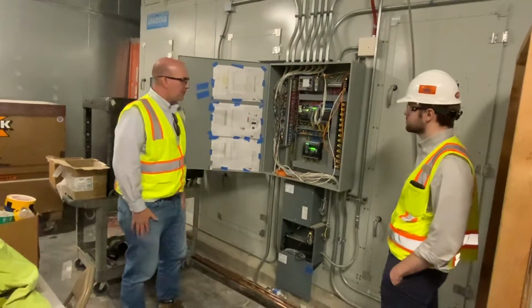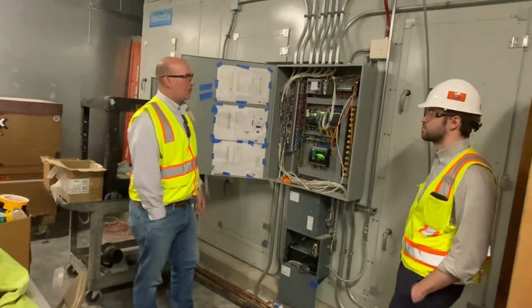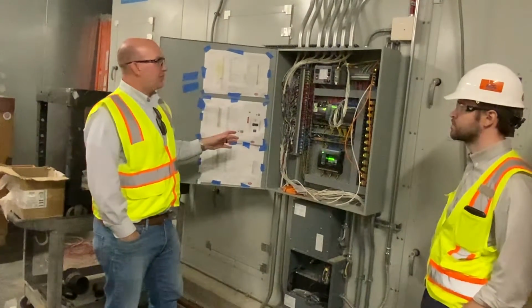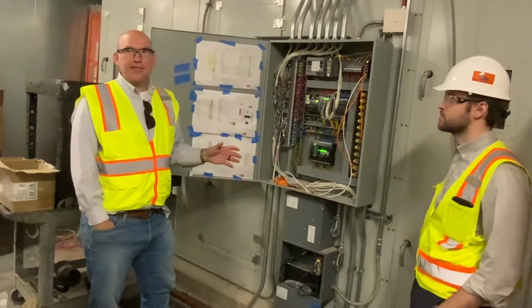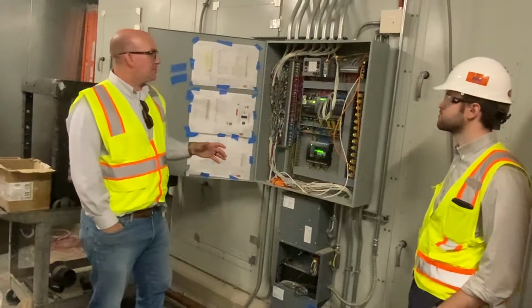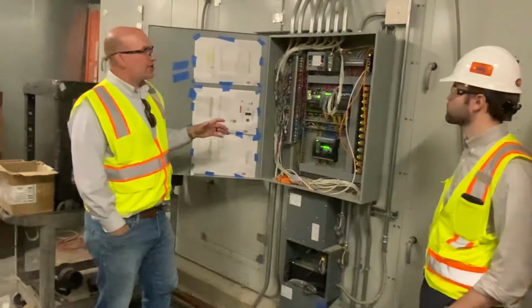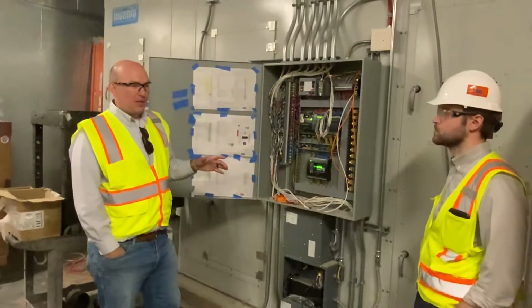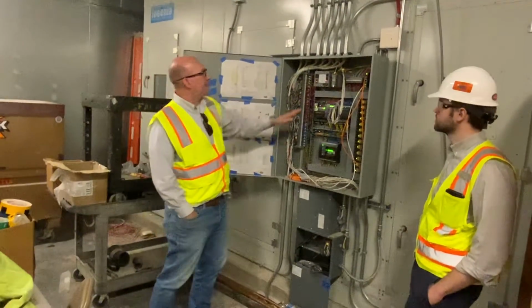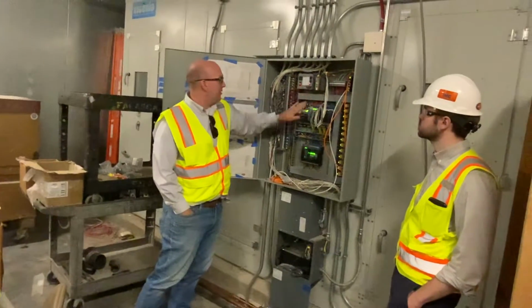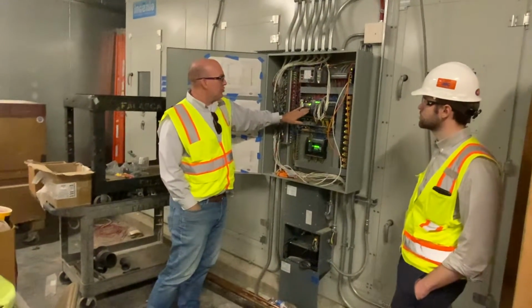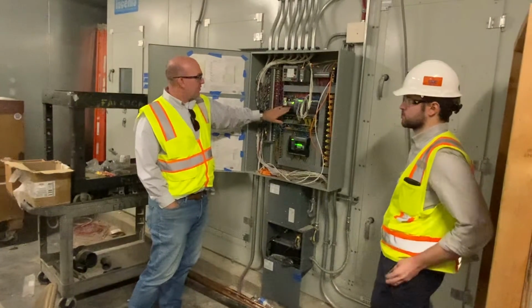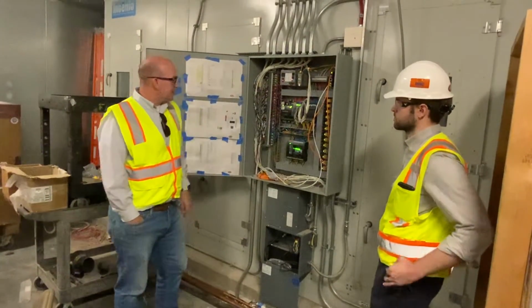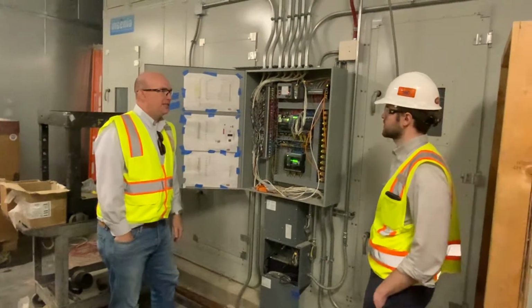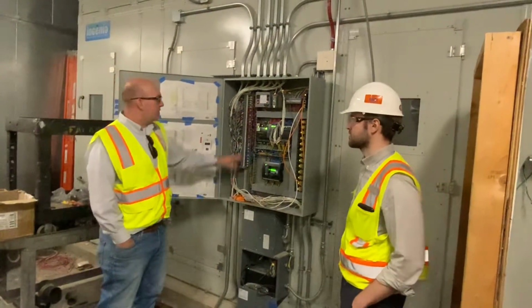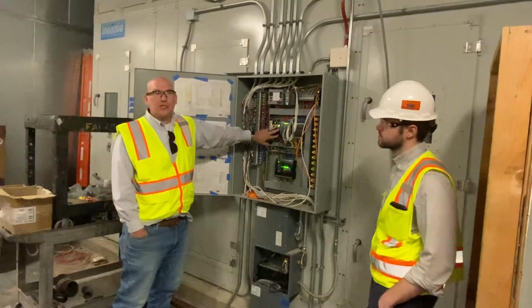Now, if you're familiar with the older installations of Automated Logic, most contractors are using regular AC transformers to power the controllers. There's a significant savings of size, not so much cost. It's a little more expensive to use DC power supplies, which is what we have here. The real savings comes in the draw from the controller. For this controller and expander, you would need, is it a full 100 VA or is it like 90? Just this controller is 100 VA. You need a dedicated transformer for it.